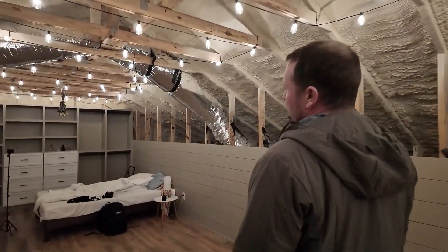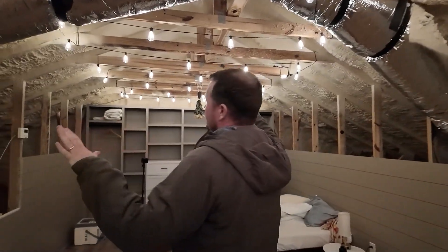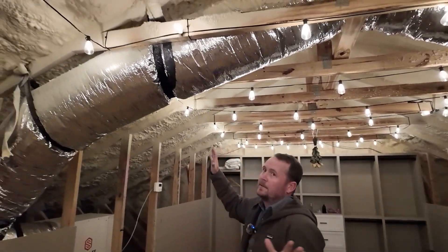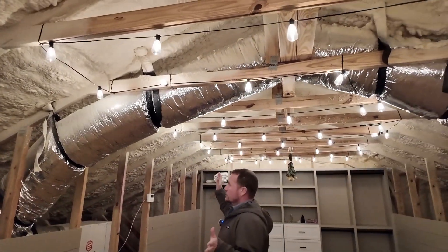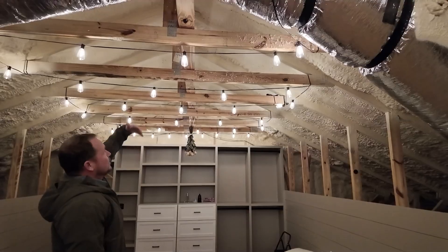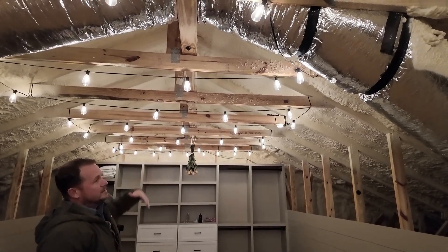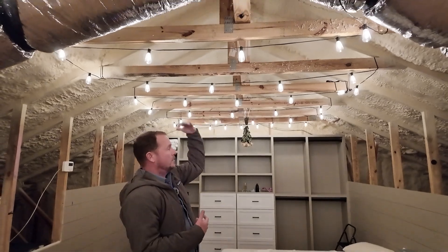We've got a problem with humidity, both upstairs and downstairs in some other areas. This is a closed-cell foam attic, and closed-cell foam is great. It adds structural integrity, it has really good insulation, but along with it, you get moisture that gathers in the peaks because of what we call hygric buoyancy.